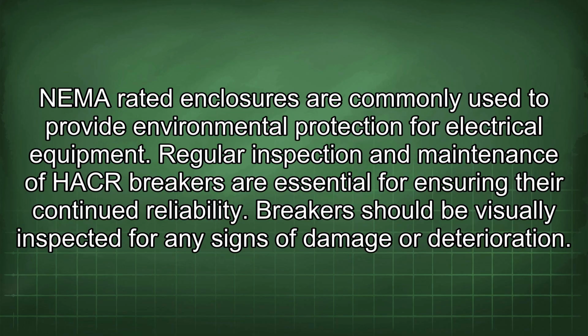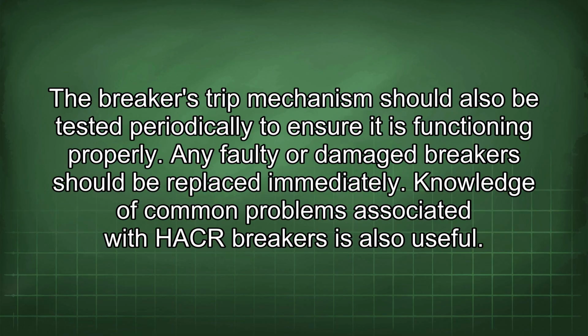Regular inspection and maintenance of HACR breakers are essential for ensuring their continued reliability. Breakers should be visually inspected for any signs of damage or deterioration. The breaker's trip mechanism should also be tested periodically to ensure it is functioning properly. Any faulty or damaged breakers should be replaced immediately.